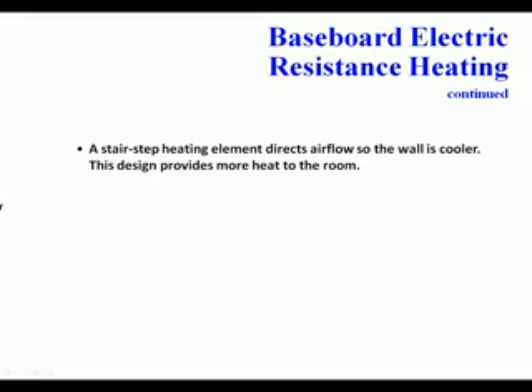Baseboard electric heat is one of the most popular forms of natural convection heating. The electric resistance coil is mounted in the casing. Warm air is light and rises. Cold air is heavier and settles to the lower opening and is then heated. The units are mounted on a wall close to the floor, usually under a window. A stair-step heating element provides direct airflow so that the wall is cooler.